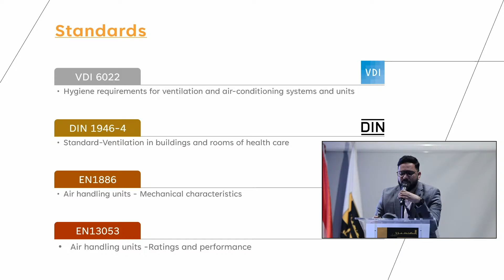And the other is the DIN 1946 Part 4, which is more of a stringent design when it comes to hygienic application. But it majorly focuses on the design of the AHU itself rather than the ventilation part or the airstream part. Along with that, the same hygienic unit also has to follow certain standards of Eurovent, which is the EN 1886, conforming to certain mechanical characteristics in the unit, and the 13053 standards.